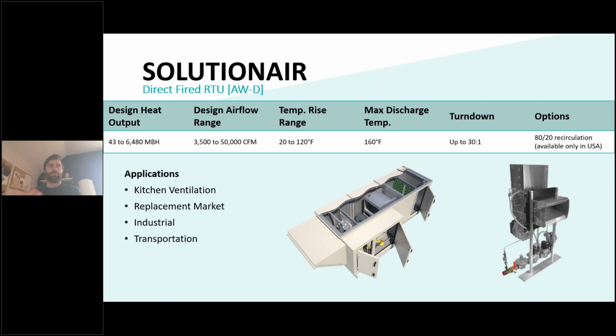And then looking at the direct fired unit, so this goes up to 50,000 CFM, really great turn down ratio of 30:1. Typically, I see this as a cheap heat option. So we find it a lot of the time in kitchen ventilation when there's high air changes per hour, or often in industrial or transportation. So different bus garages will often have this style of unit in there if they're looking for a gas heat option.